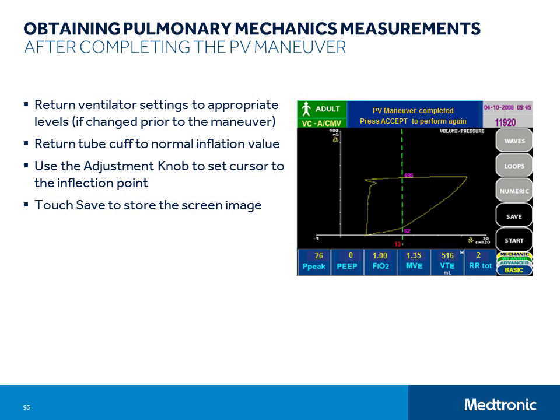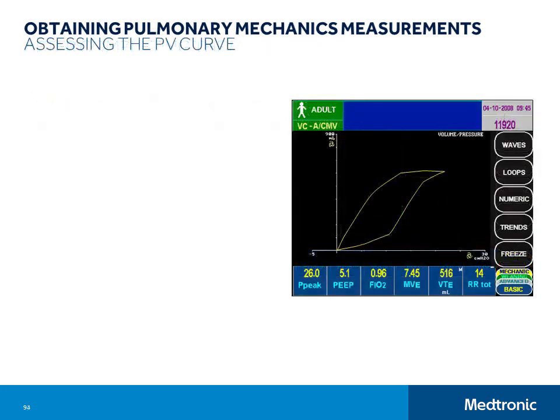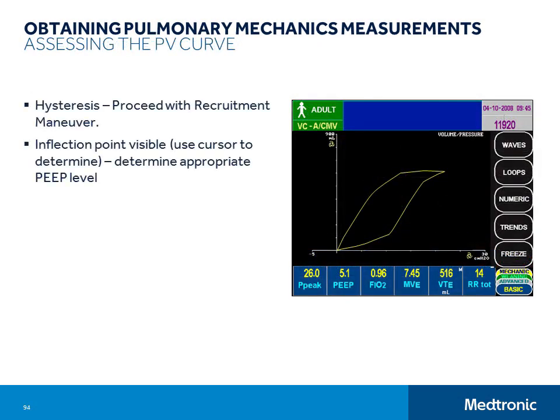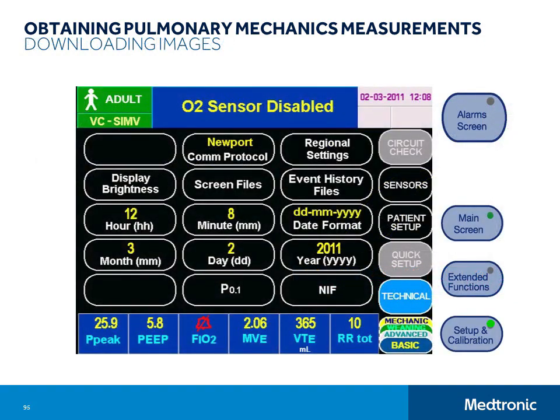After you have saved the screen to memory, it's very simple to download the screen image of the curve to a flash drive so that you can view it on a computer screen. Press the Setup and Calibration button on the control panel, touch the Technical button on the GUI, and then touch the Screen Files button. A scrollable table of the corresponding save files will appear. Install a USB flash drive version 2.0 or later into the USB port on the back of the ventilator, and then using the adjustment knob, highlight the file you want to download and touch the Download button.